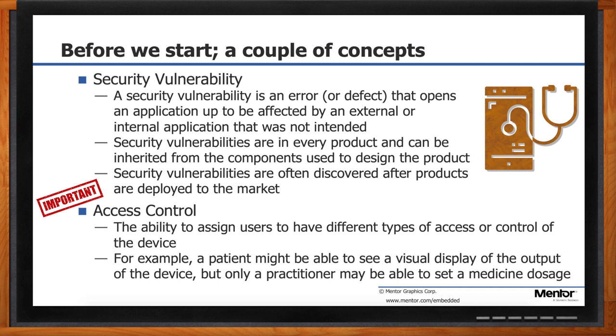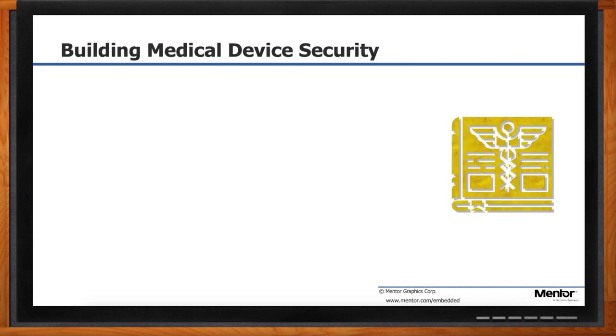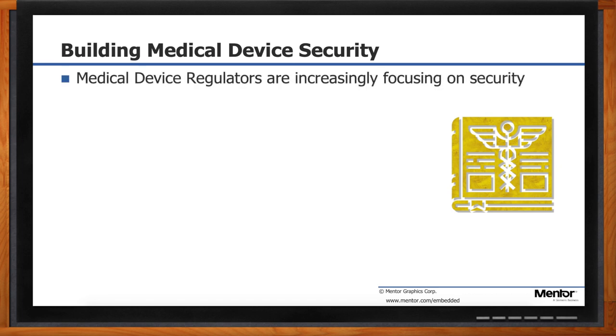Regulations and life cycle concerns also come into play here. When you're developing a medical device, what you've been worried about is: does it do what you intend it to do, and is it safe to be used on a patient? What you're trying to do is provide benefit to the user while minimizing potential harm. Anyone who's watched a commercial for a drug knows there are side effects — same thing's true with devices. What regulators are looking for is whether the bad things are not nearly as bad as the good things the treatment will achieve.